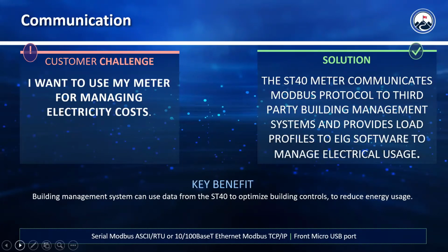If you have an existing building management system and you want to be able to collect data from this meter and then use it to manage your electricity costs, the ST40 meter communicates Modbus protocol to any third-party building management system. So if you already have an existing system in place, you can use the ST40 meter and integrate it over the Modbus protocol, and you will be able to look at all of the load profiles and look at all of the data. In addition, you can always use the Energy PQA cloud solution, which is a great fit for this meter. You can just go onto your browser, type energypqa.com. There's no software you have to install. It's really easy to use. And right there on your browser, on your laptop, on your phone, you will be able to look at all of the data of how your machine is operating.